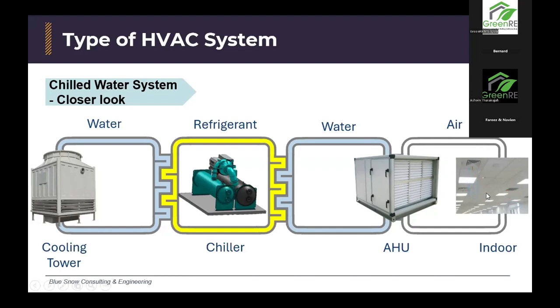So the heat from the air is transferred to the water, and then the water brings the heat to the chiller. The chiller consists only of refrigerant, which is never in contact with the water. So the water and refrigerant will not mix. It just passes through a coil. The refrigerant goes through a coil. So this part is actually the evaporator, and this part here is the condenser. So this is the part of the chiller.